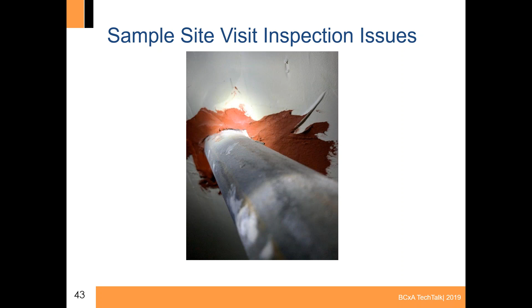I guess if you think about it, that's similar to fire dampers. A lot of contractors want to test their fire dampers right away, and then we go and put in ceiling grid, fire alarm devices, grills, and lights, and suddenly the access point to your damper is gone. So it's important to test those late in the game so you can truly verify they give access to move the damper, adjust and reset the linkage, and all that kind of fun stuff.